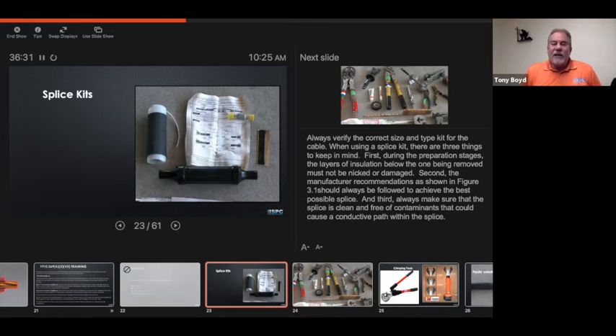And you notice it's got a little bubble in the inside. This is very important for the stress in that splice body. If it gets offset too far one way or the other, and right here. So if this part gets offset inside that splice body one way or the other too far, it will actually create a stress point in this area and cause a fault across the grounded outer jacket.